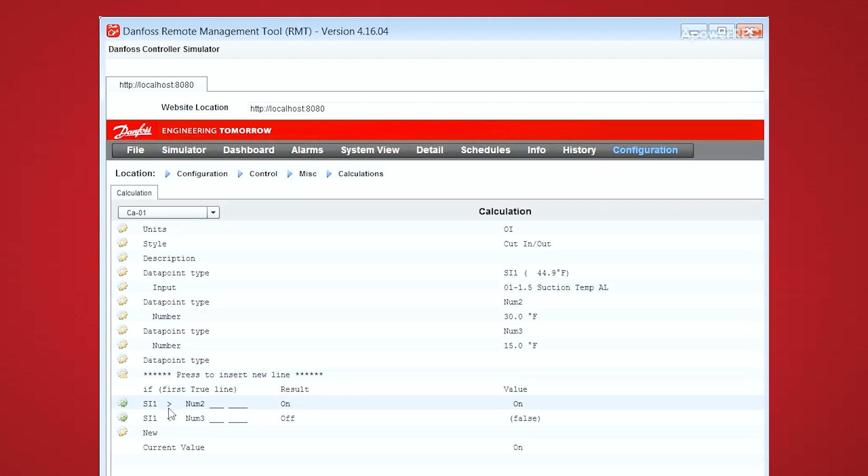So as you can see down in the bottom part, if the sensor input 1, which is the suction temperature, is greater than number 2, which is 30 degrees, then this calculation will evaluate as on.